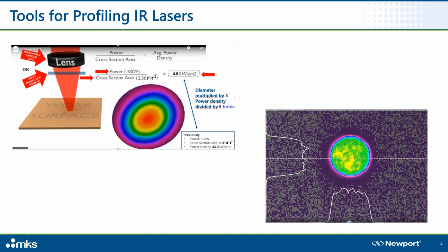So you were able to monitor the power density or radiance profile that the laser operator needed to know to determine if the laser was operating correctly. Here is the standard top hat or uniform laser beam profile. You can see the false color image as well as a 1D or slice through that image showing the relative intensity profile of the beam.